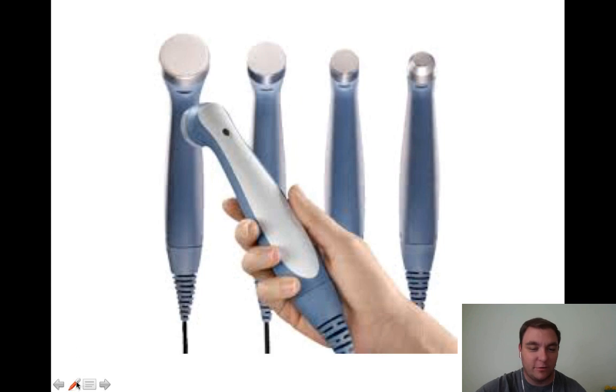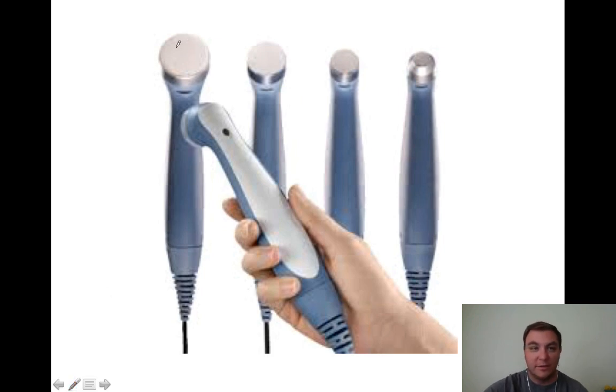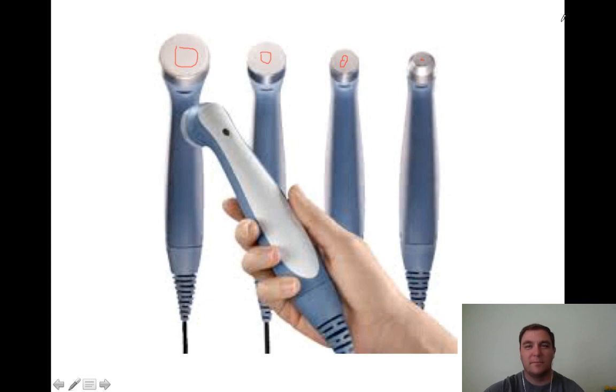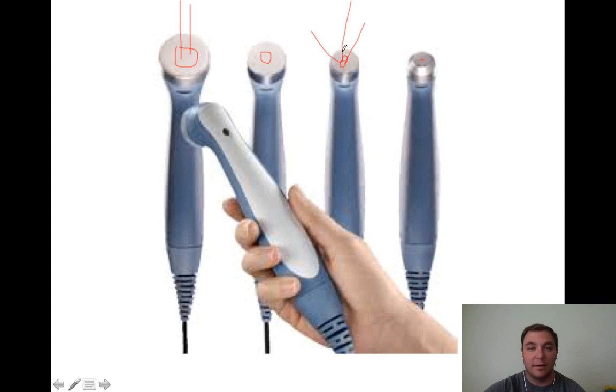These are different ultrasound heads you can buy for a unit - the ERAs will be different for all of them. The larger ERA produces a more collimated beam; the smaller ERA produces a more divergent, cone-like beam.